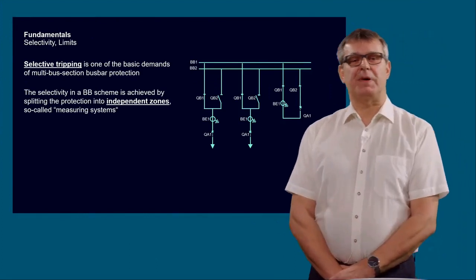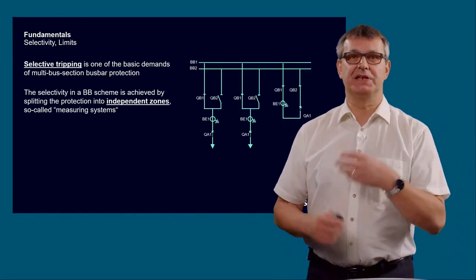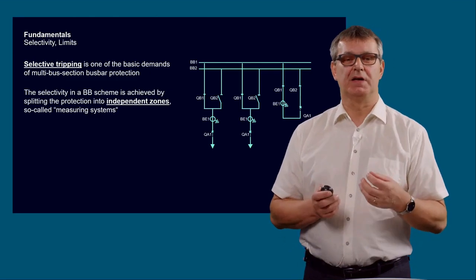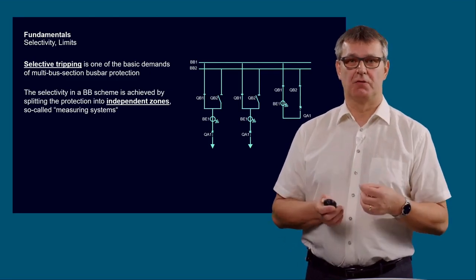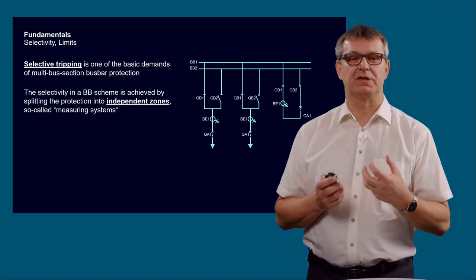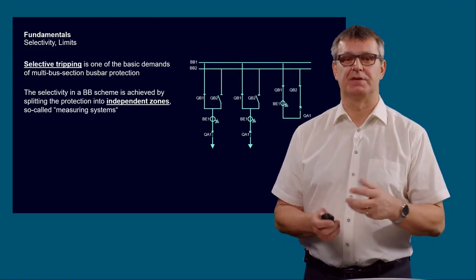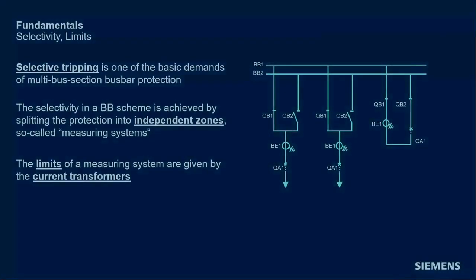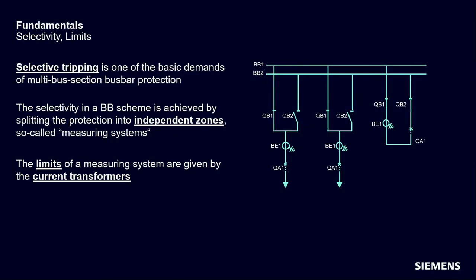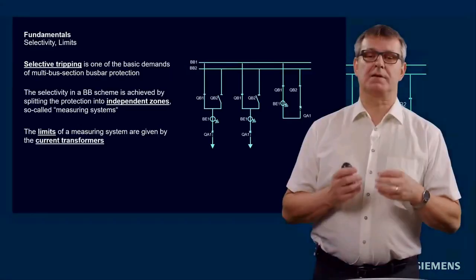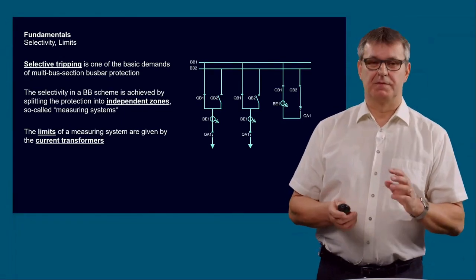Selectivity in a busbar protection scheme is achieved by splitting the whole busbar into independent zones. We call them measurement systems or measuring systems. And as it is a differential protection, the limits of the measuring systems are, as in every differential protection system, the current transformers. So the area will be limited by the current transformers.